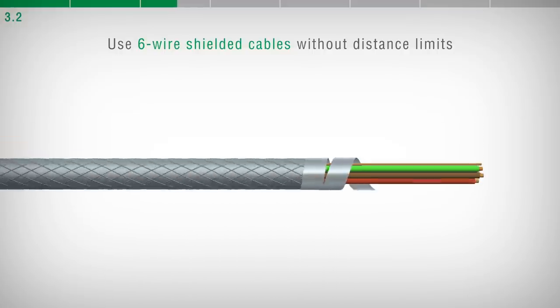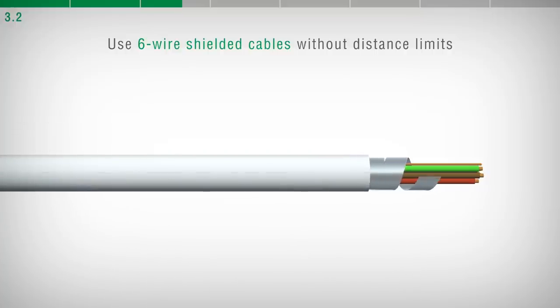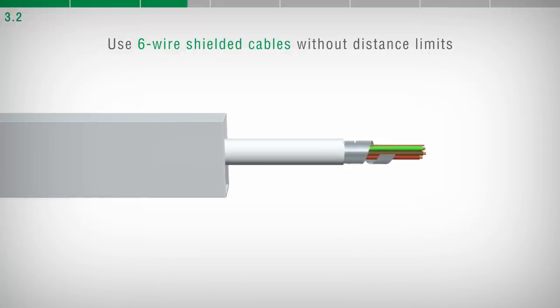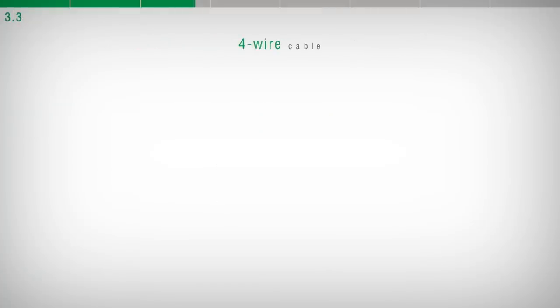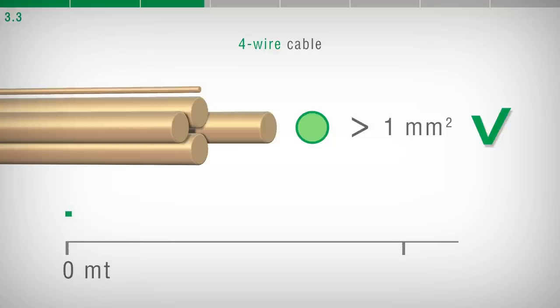Ideally, it must be inserted alone into the wire way and laid as far as possible from the power cables. When using four conductor connection cables, consider a minimum section of one square millimeter and preferably not exceed 300 meters in length.